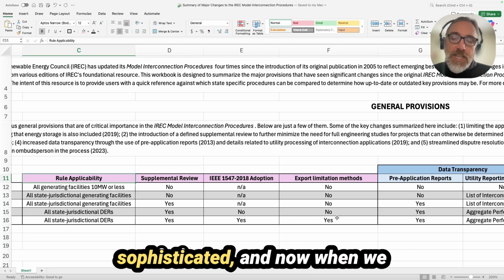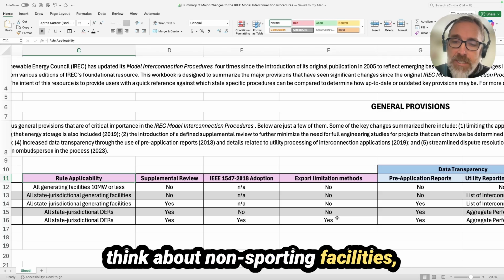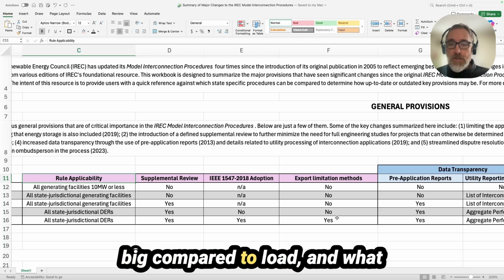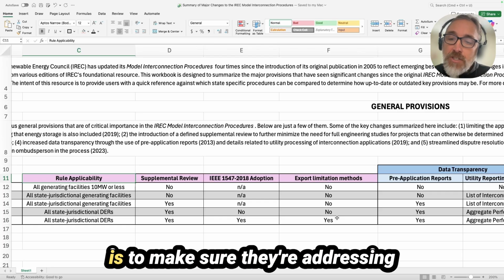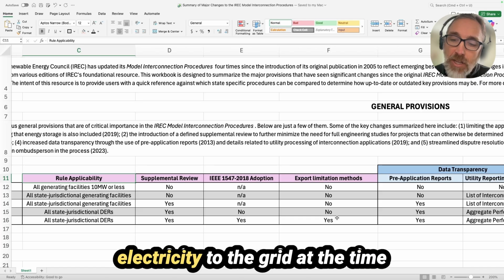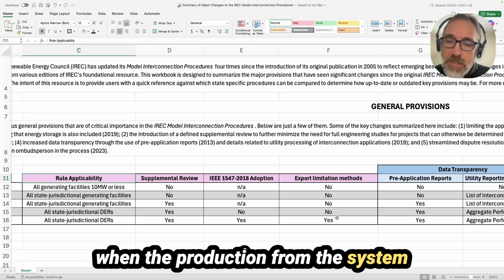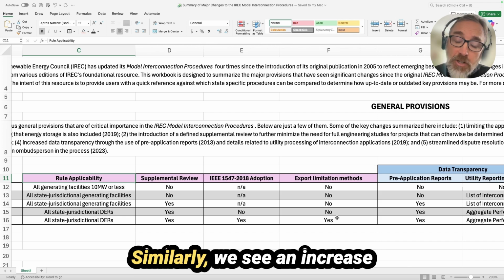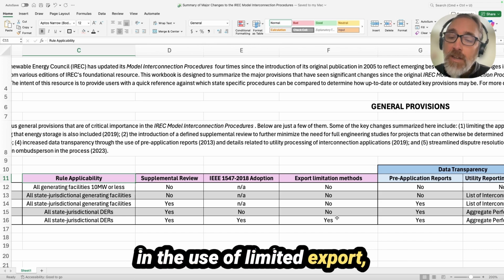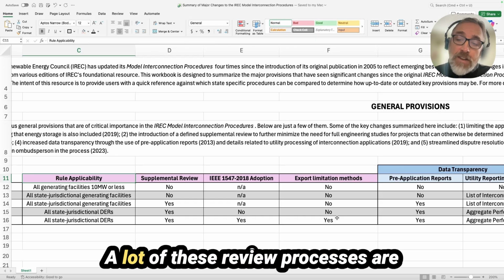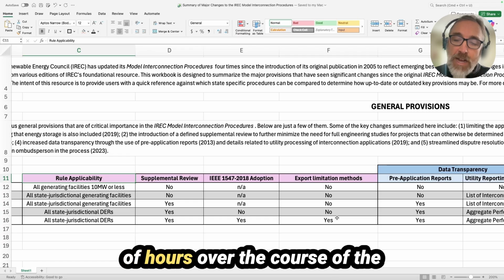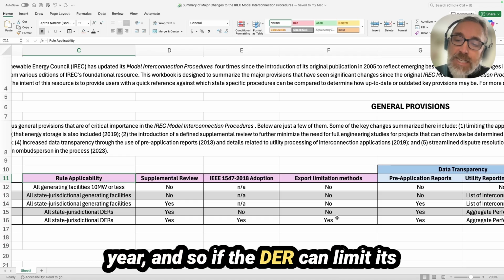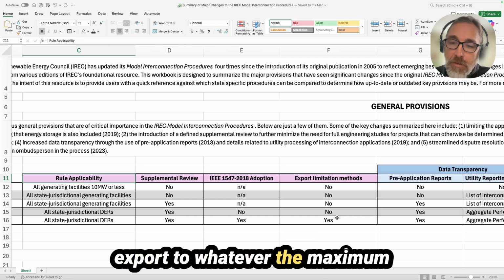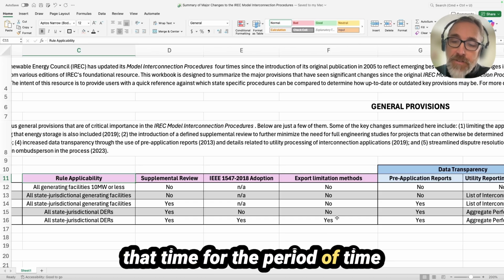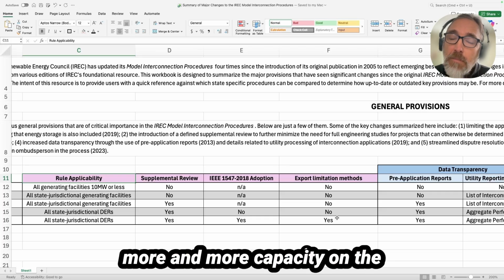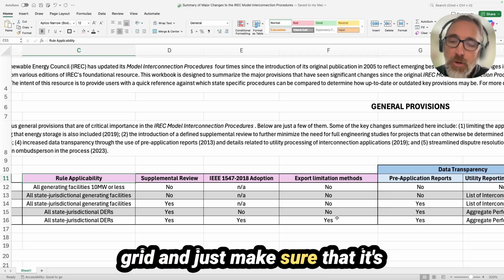Over time, things have become more sophisticated. And now when we think about non-exporting facilities, it may be that the project is quite big compared to load. And what the system owner is trying to do is to make sure they're addressing grid constraints by not exporting electricity to the grid at the time when the production from the system might exceed the load in the facility. Similarly, we see an increase in the use of limited export, and that's to deal with specific constraints on the grid. A lot of these review processes are looking at just the worst handful of hours over the course of the year. And so if the DER can limit its export to whatever the maximum is that the grid can handle at that time for the period of time where there's a constraint, then there is the potential to put more and more capacity on the grid and just make sure that it's responsive to the needs of the grid.